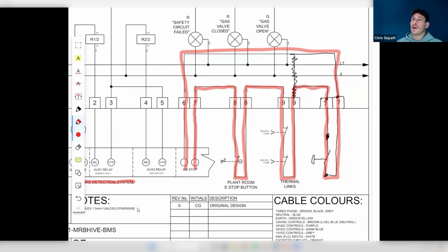Yeah. So again, this is something that in industrial environments where you're using things like safety relays, where it's safety critical, like there's moving machinery that can ultimately kill people, then in safety circuits that are using safety relays, you need to add that additional redundancy where you have two contacts on the e-stop and they're working together, so you might have a normally open and a normally closed, and you hit that and it inverts both of them, but then back at the panel, the safety relay needs to see both of those change at the same time to tell it that it's working okay. And if it doesn't see that, then there's a problem and it shuts down the system. Yeah, it's just redundancy and different levels of redundancy.